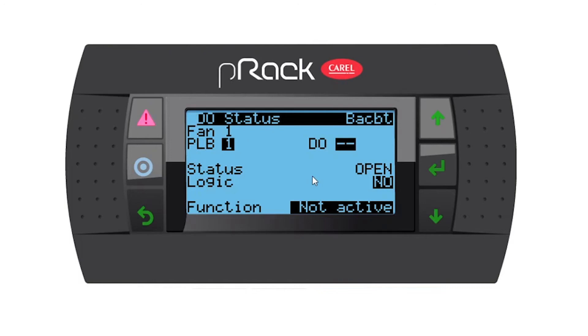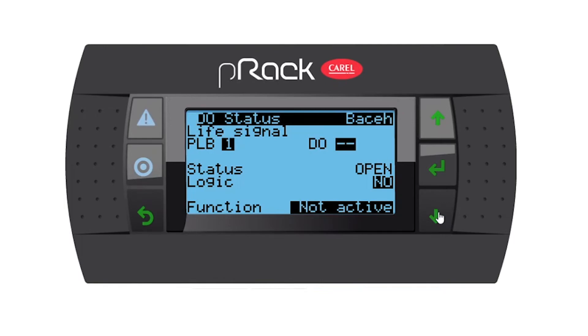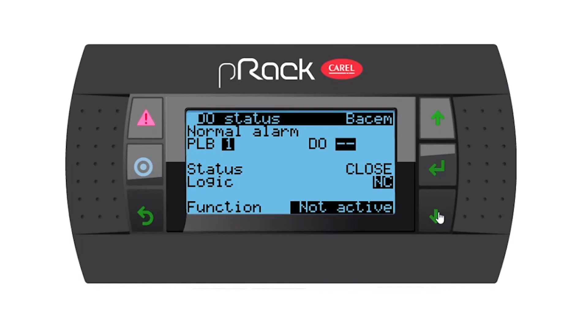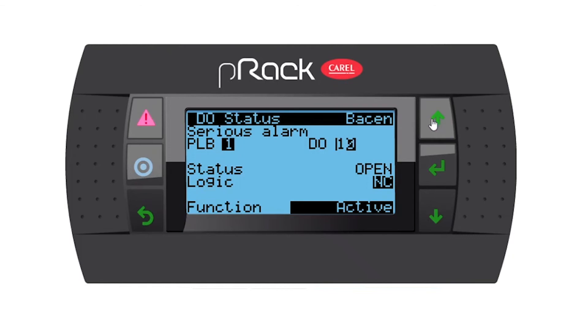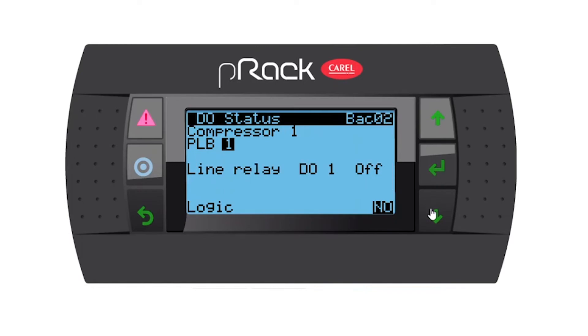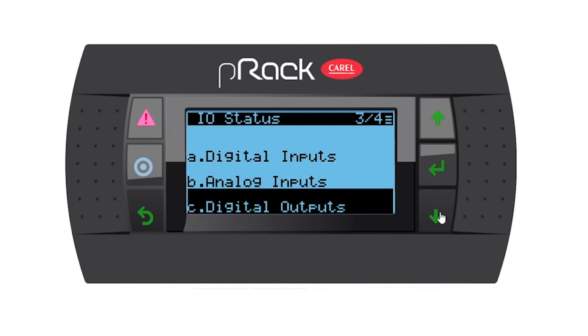For fans, you have the option of a fan enable, but remember we said we have an analog fan — inverter fans — so I'm not going to assign this digital output. Do we have a global alarm output? No. A life signal? No. BMS force output? No. A normal alarm? No. But yes, we have a serious alarm, so I'm going to assign this to number 13, normally closed for this video.